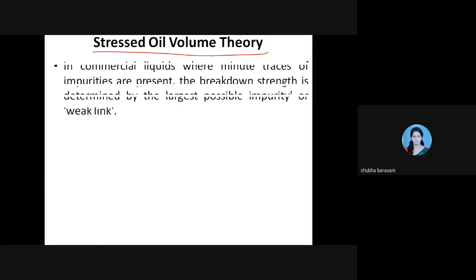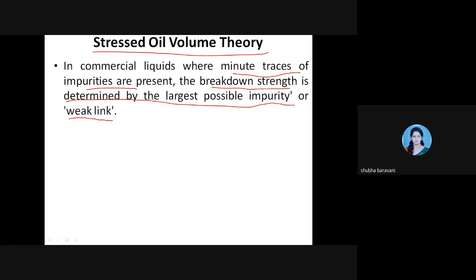Today we see the third theory, called the stressed oil volume theory. In commercial liquids where minute traces of impurities are present, the breakdown strength is determined by the largest possible impurity — the weakest link. Commercial liquids contain complex hydrocarbons. If a dust particle is present, those dust particles will have greater affinity and will be more conductive.